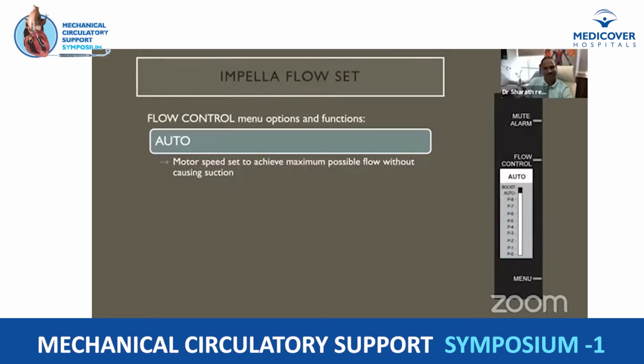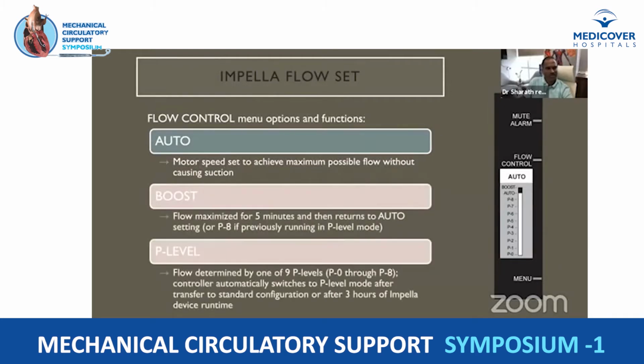So based on that, we can check positions, and we can adjust the position of Impella. Coming to setting flow, you have three options here. First, the auto flow option. In auto flow, motor speed is set to achieve the maximum possible flow without causing any suction. This is what we use most often in protected PCI, but it works for only 3 hours. After 3 hours, the device automatically switches to the preset P level. In P levels, we can have different options from P0 to P8. P0 means no flow, P8 means almost the maximal flow.